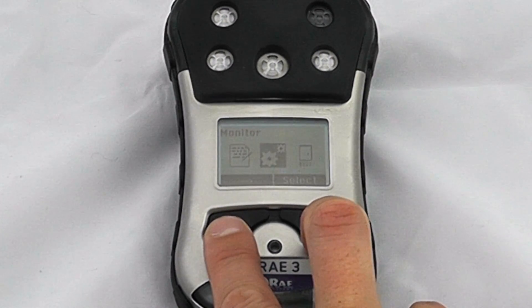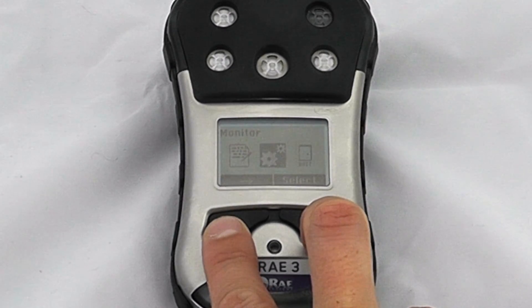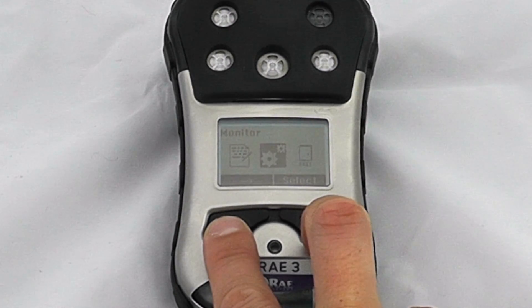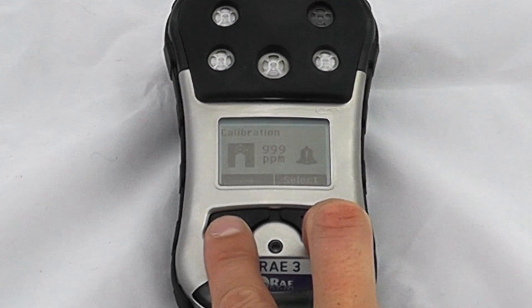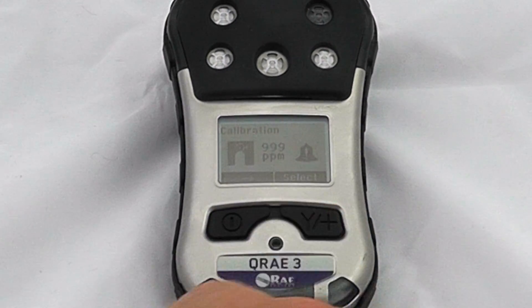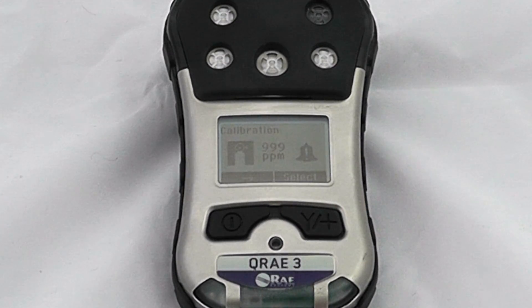Measurement criteria includes correction factors for LEL sensors, and there are alarm settings for toxics, data log settings, and general monitor settings which can include wireless if enabled. This happens to be a wireless device. We also have the option to enable and disable sensors. This is a standard four-gas instrument: O2, CO, H2S, and LEL. SO2 sensors are also available.